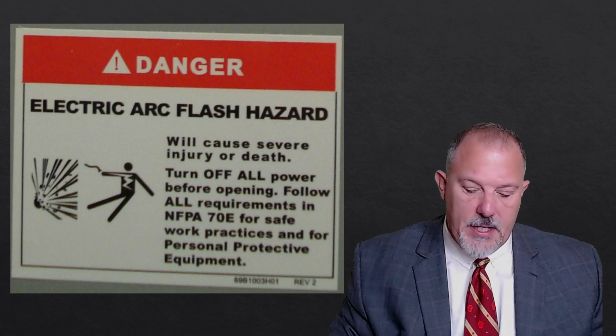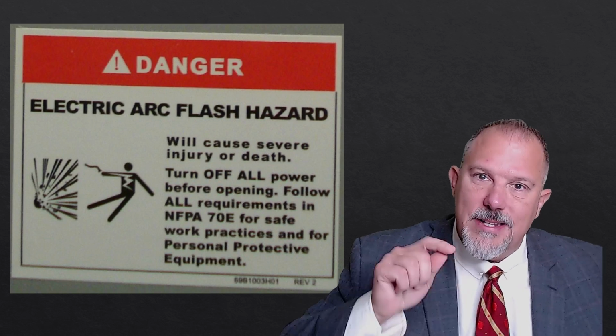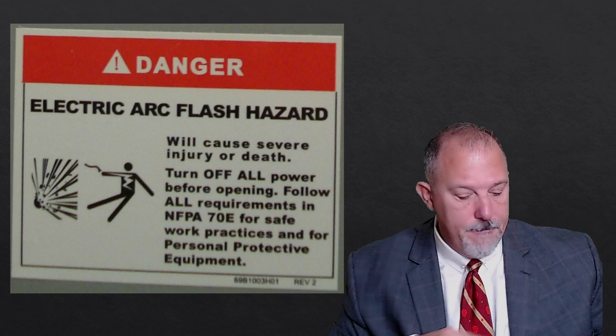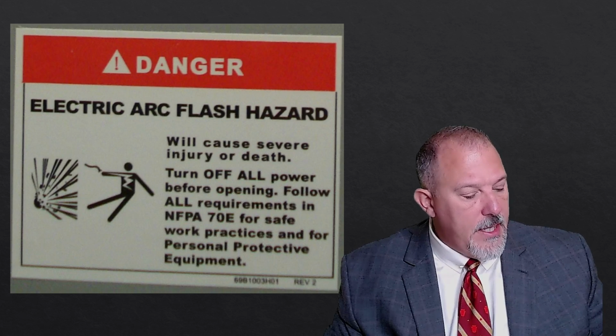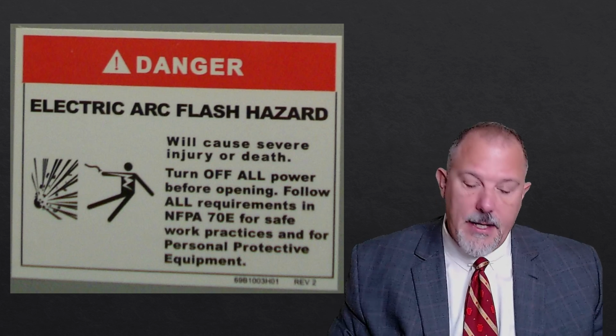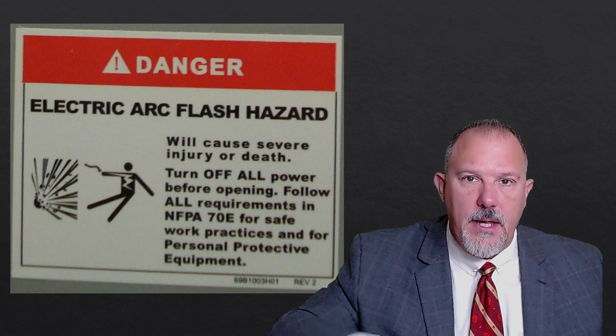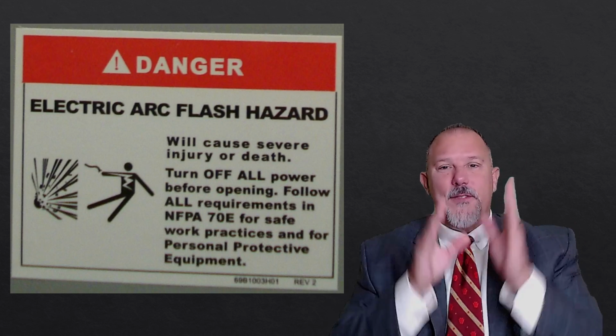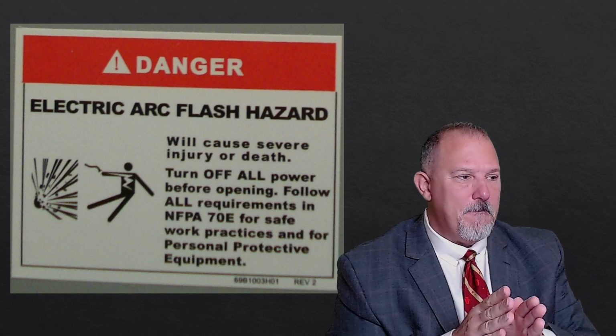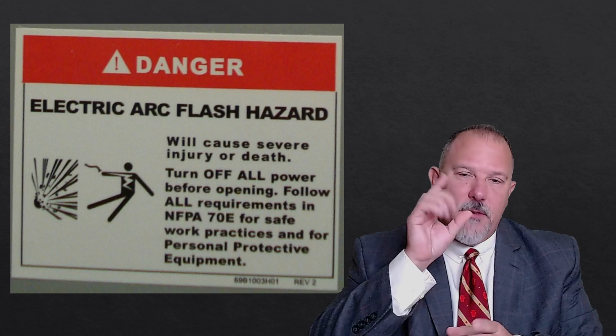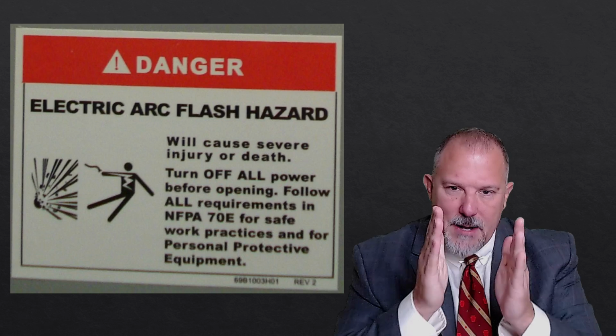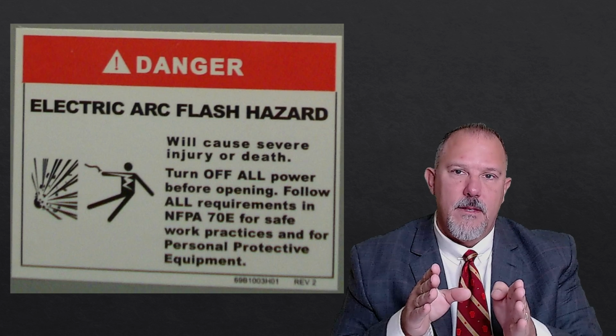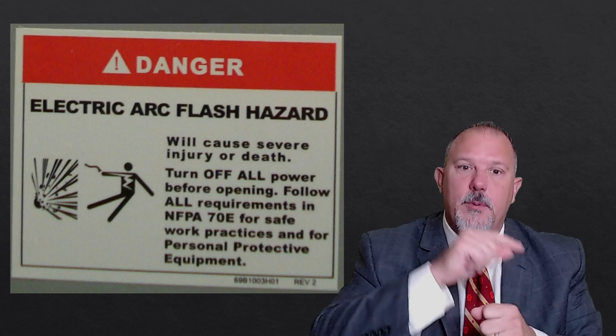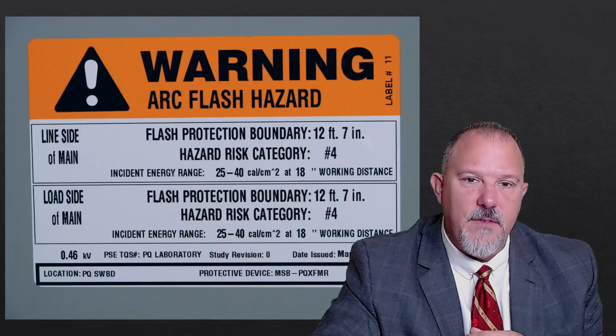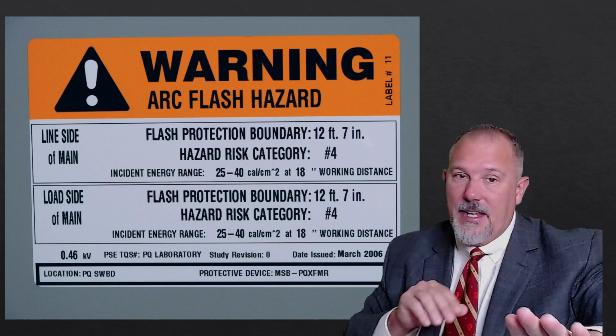The parent text tries to speak to the table method, which is in 130.7(C)(15)(A). And I think there's a B as well for DC systems, but you have an A and a B to help you determine PPE. But I'll tell you, there are a few changes, and I want you to be mindful of this. Let's think about a panel board with 6 disconnects. If I have a panel board with 6 disconnects, does this mean I need to put 6 of these types of labels?